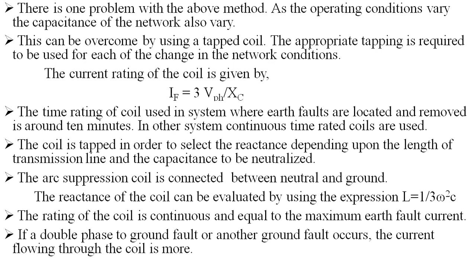If a double phase to ground fault or another ground fault occurs, the current flowing through the coil is more. See, there is the arc suppression coil which is having the tappings such that the required resonance can be observed over here. Here is our earth fault relay and the DC supply for our tripping circuit.